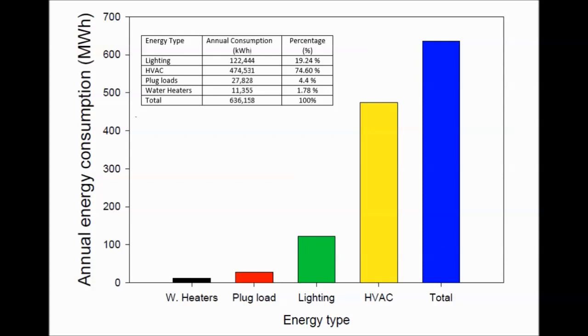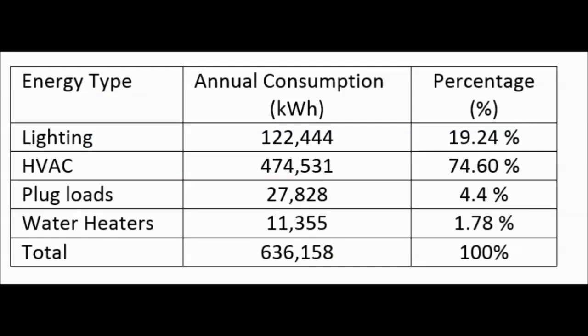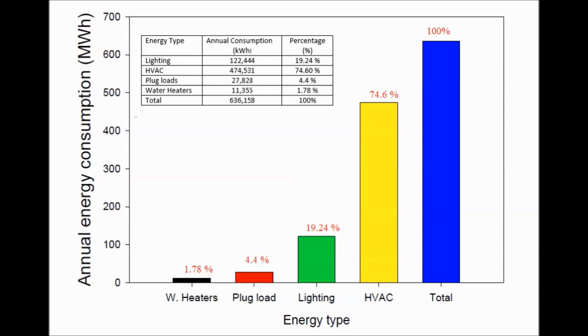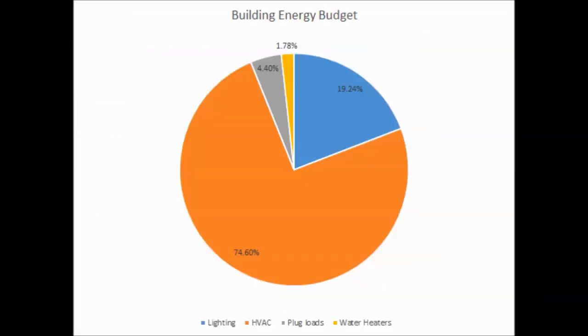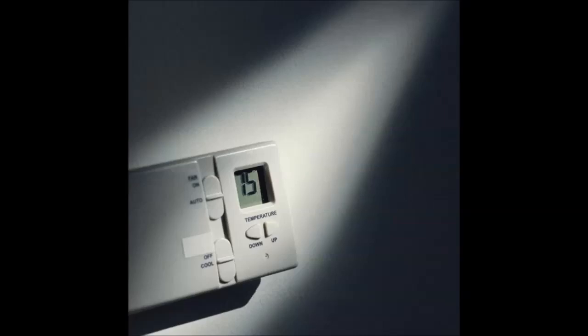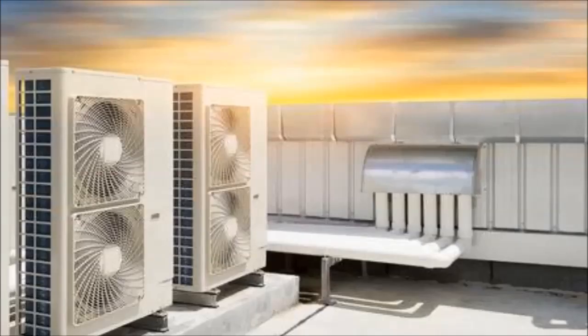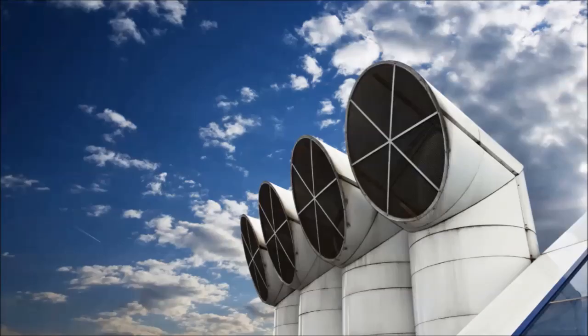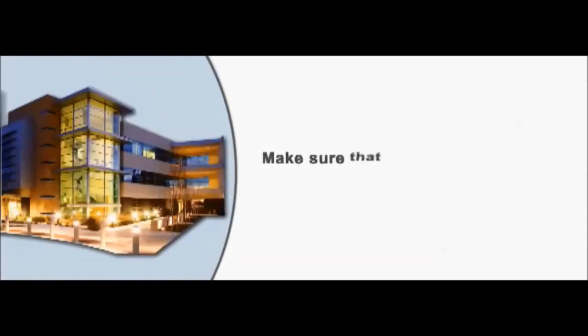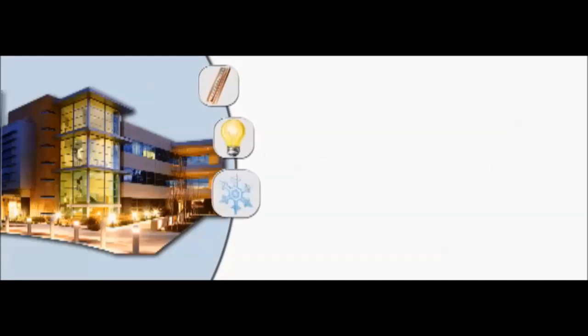The air conditioning system was found to be the major contributor to energy consumption by a percentage value of 75%, followed by the lighting system with almost 19%. The plug load share was almost 4%, and the water heater's consumption was less than 2%. Hence, the work chose to focus on air conditioning strategies, both passive and active, as well as solar water heating system, to lower the annual energy consumption of the building. The argument for this selection is that air conditioning makes most of the building energy consumption, and saving 15% of air conditioning consumption, which is achievable, is almost the same as saving 66% of the lighting system, which is almost impossible. 4 air conditioning passive strategies were used to lower energy consumption of the building.